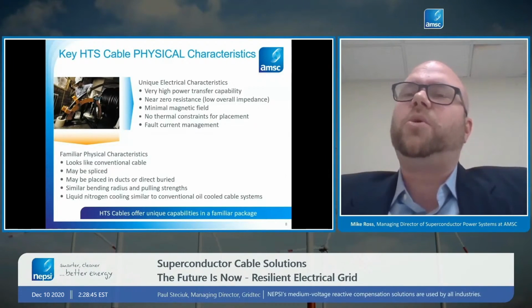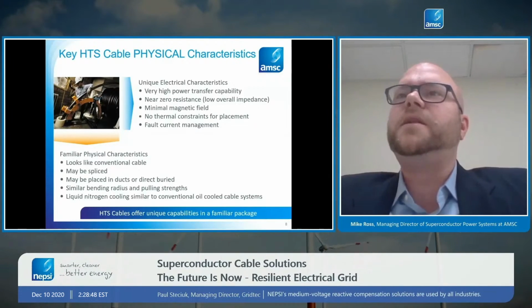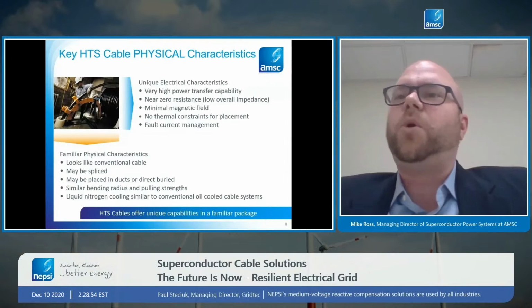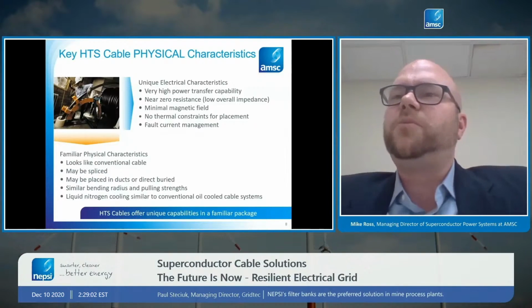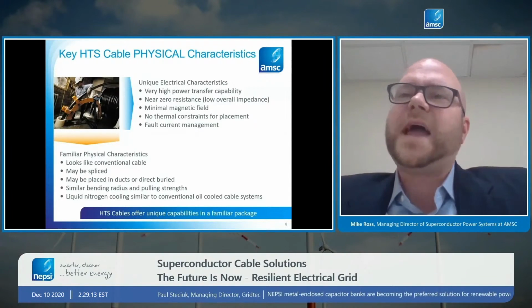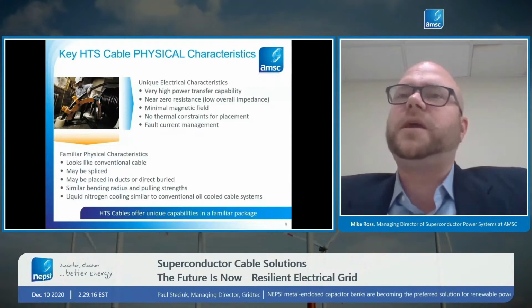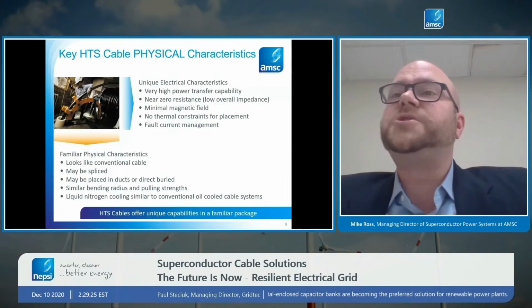So I had mentioned earlier about those oil-filled cables or pipe-type cables. In about 30 or 40% of those applications, the utility will circulate oil through those cables. The oil will flow through the cable and pick heat up off of the cable, and then somewhere in a substation, there's a heat exchanger that the hot oil flows in, the heat's removed, and then cool oil is flowing back through the cable. That's exactly what we do to cool our superconductor cables, but we do it at a much lower temperature and with a much safer and more environmentally friendly material, liquid nitrogen instead of mineral oil.